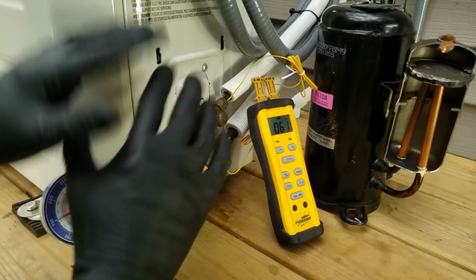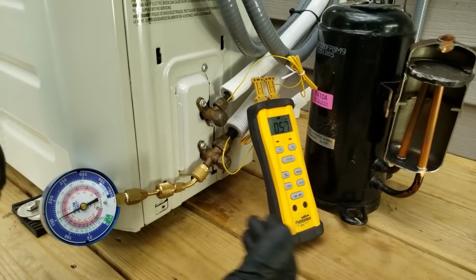So when you're trying to quote unquote check the charge, there's a lot of factors that are going to change what your refrigerant charge level is. You don't know the speed or the capacity of the compressor. You don't know the speed of the outdoor fan, the indoor fan. Is it set on auto or is it set on medium? Do you have it all the way up on high speed, your indoor fan? Because then you're going to have a higher heat load at that indoor coil. These systems measure these thermistors maybe every 20 seconds, 30 seconds, maybe every 2 minutes, and it's making operational decisions and changes that you don't know. And so the manufacturer would have to give you some way to lock the system at a certain amount and give you like a target superheat guide that it should be ranging at.